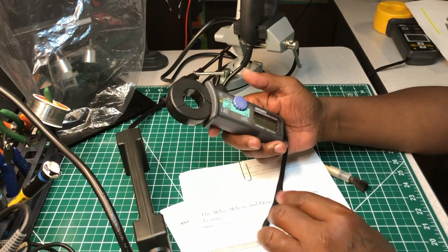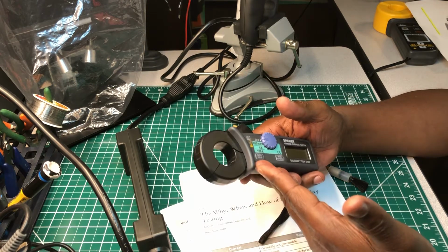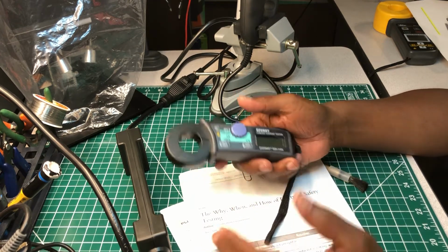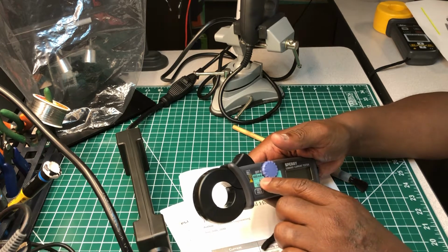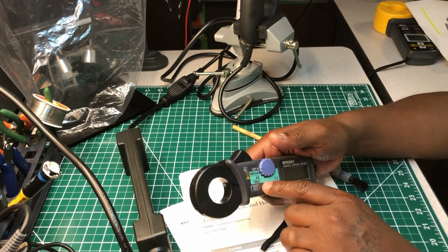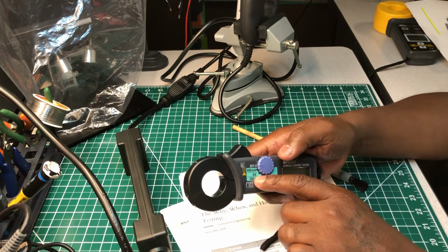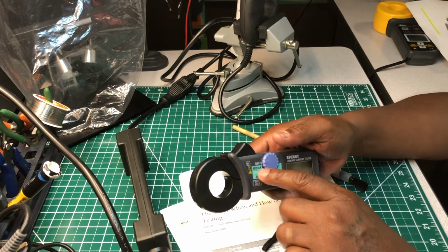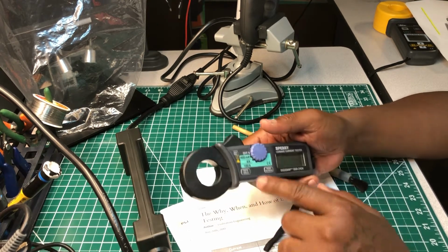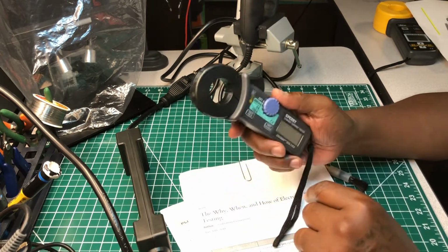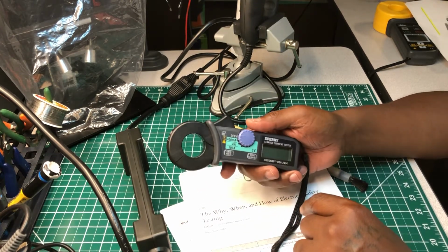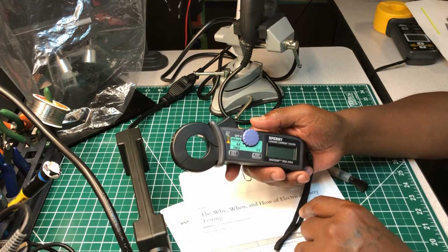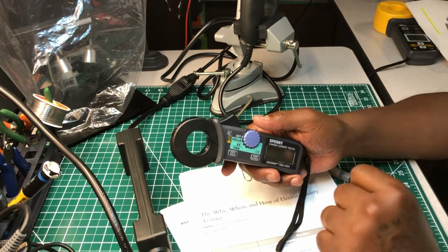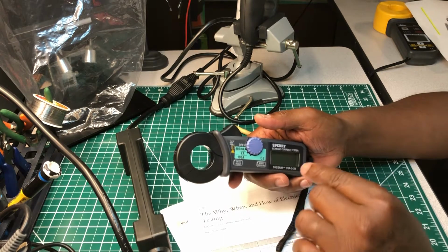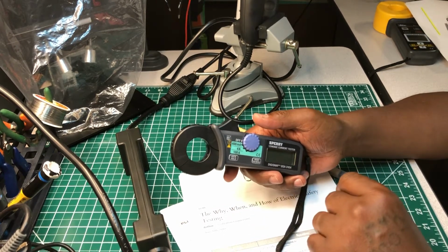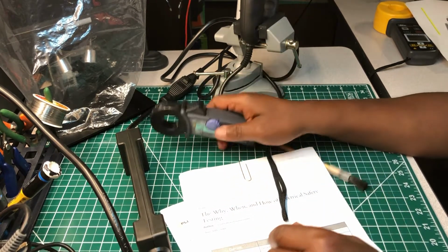So you've basically bought yourself a regular clamp meter, because it won't go that low. So watch what you're buying. The milliamp measurement is very important. Don't worry about the other two, like the 100 amp and the 4 amp. What you want is the milliamp amperage measurement. Get one that starts off at 0 if you can, or 1 milliamp, and then on up. The higher it goes, the better, but the lowest it goes is very important too. So I wanted to tell you guys that.